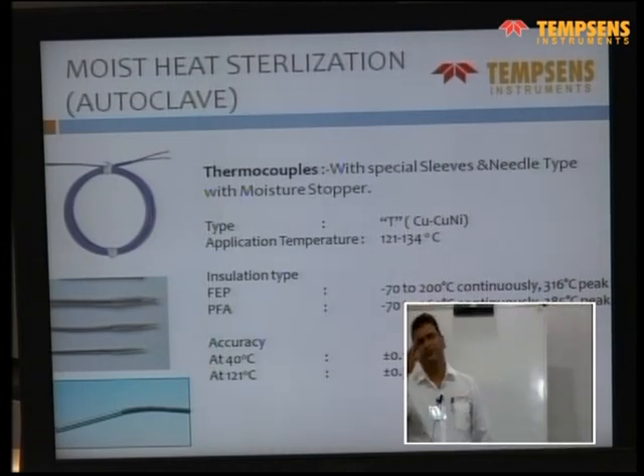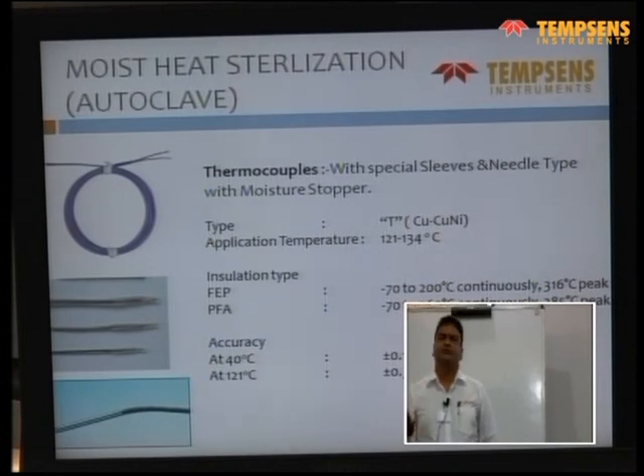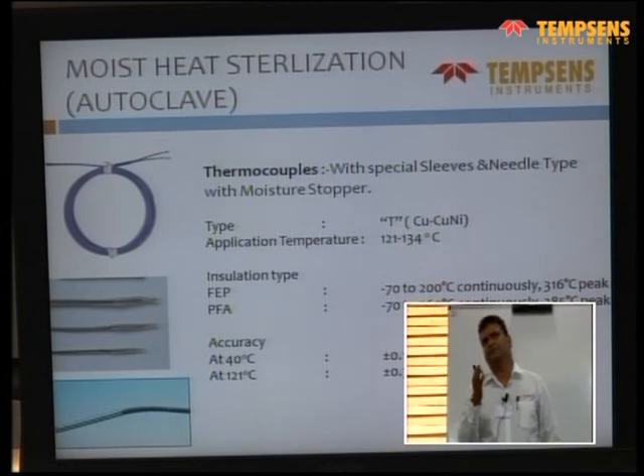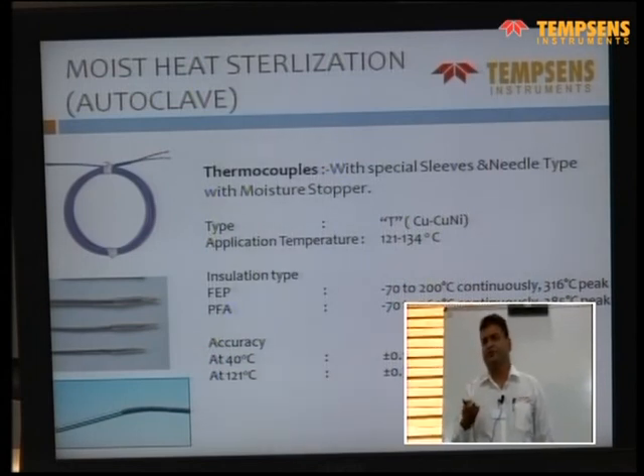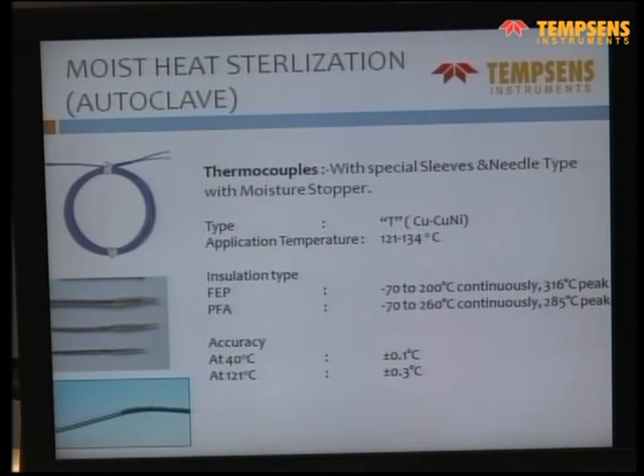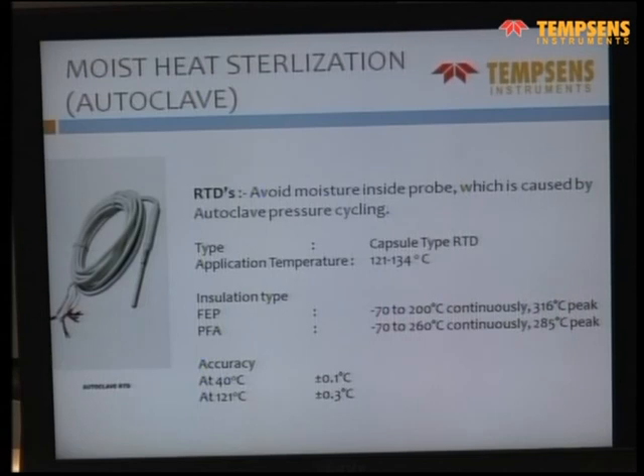As you see the ring, it's not just the normal wire or compensating wire. We use thermocouple wires, and they are insulated with Teflon in this case. So even with high pressure, the water should not come out from the other side. That's the application in the pharma industry. There are various sensors, and all of them are required at high accuracy, so they can be manufactured. This is again for autoclave. For the pressure boundary, you can see there's a special silicon encapsulation at the end of the stainless steel part, so that the pressure does not leak through the cable.